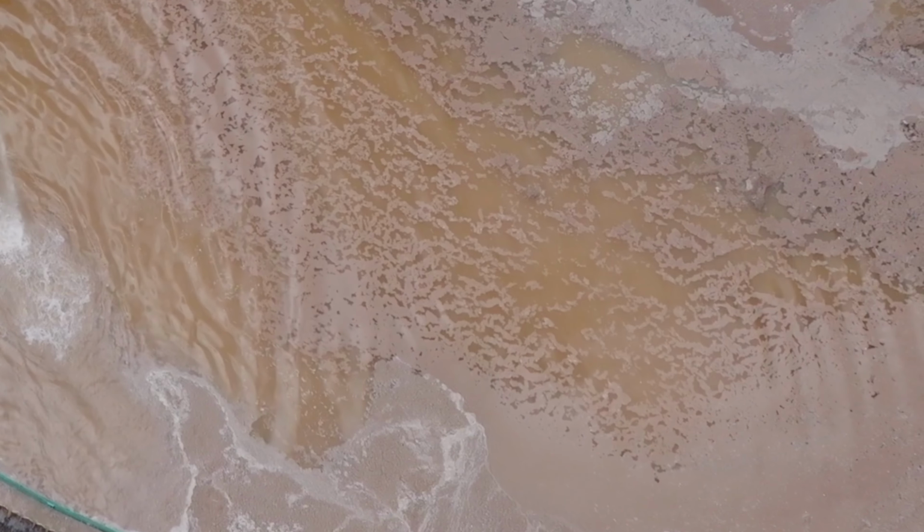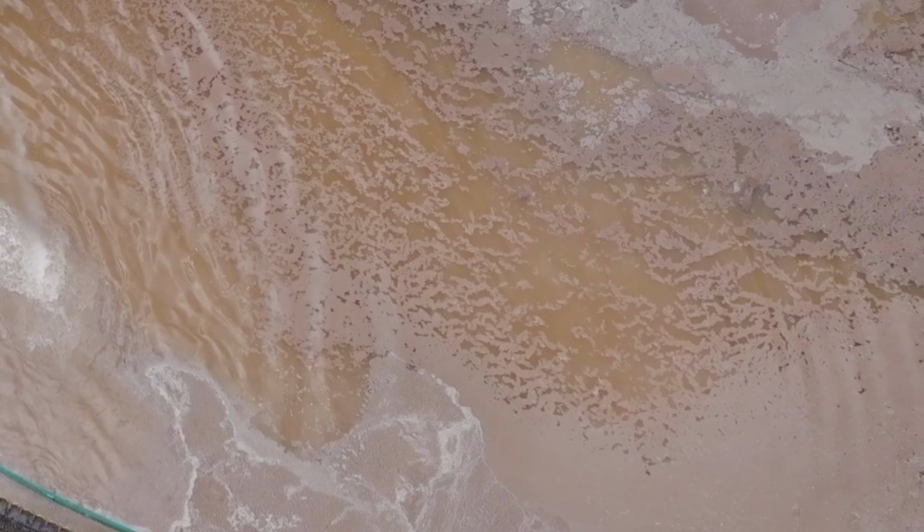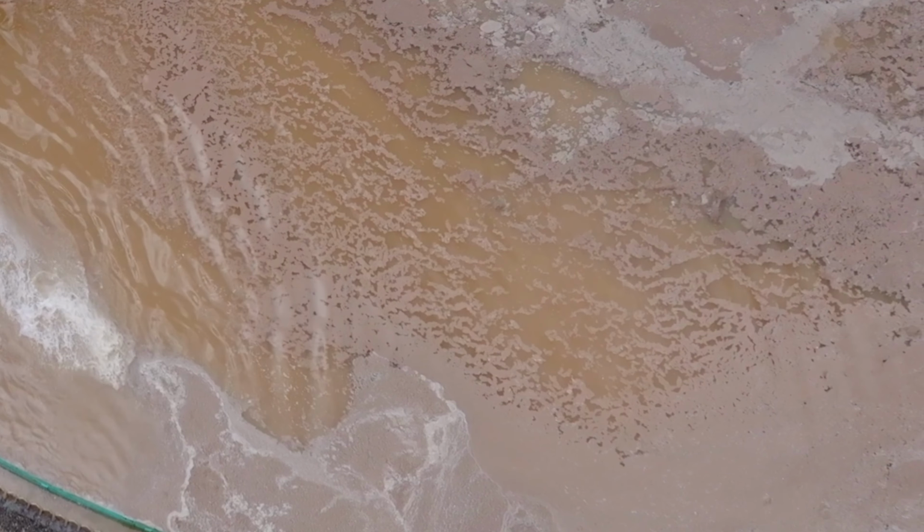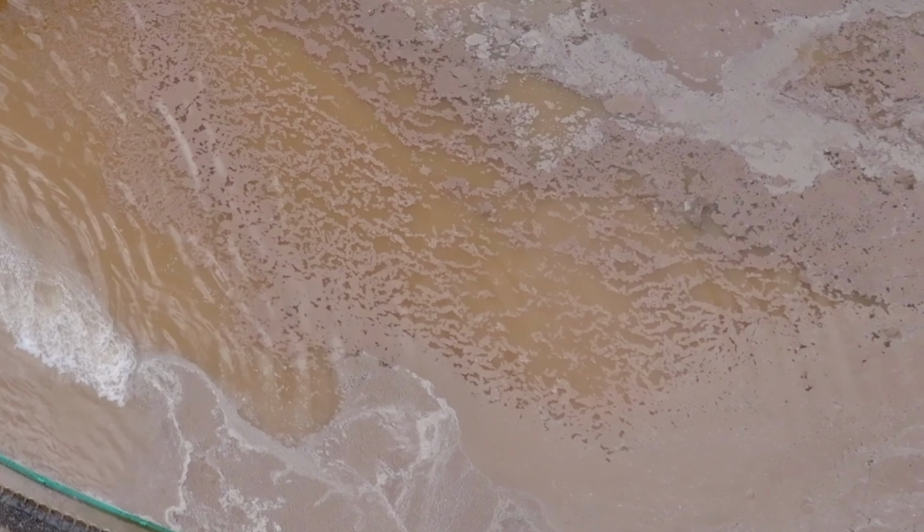Heavy metals can trigger a cascade of failures with severe downstream consequences. The initial interaction occurs within the biological reactor, where metals disrupt critical life functions of the microorganisms, causing the widespread death or incapacitation of the biomass, which brings the biological treatment process to a grinding halt. The second-order consequence is the contamination of the plant's sludge. Therefore, a single industrial discharge of heavy metals transforms the plant's primary byproduct from a potential viable resource into a long-term, high-cost liability.